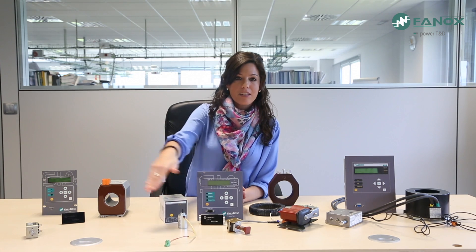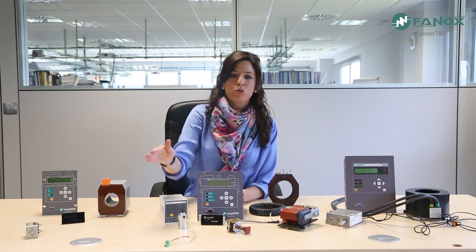Fanox relays are able to trip all the strikers offered by the market, allowing Fanox to give support to all clients on this issue. It is also possible to use a self-powered relay in a cell where a coil is installed instead of a striker. The answer is yes — the relay can be installed, but an additional device is required to provide sufficient energy to trip the coil.